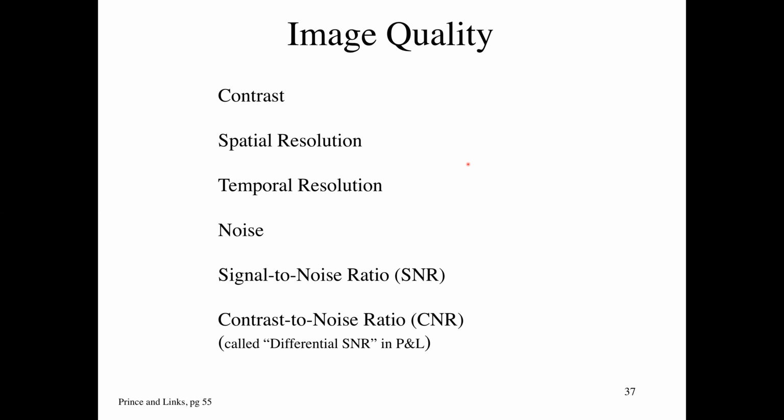Noise in MR is actually a natural phenomenon. If you take a coil and you don't elicit a signal from the patient, but you have your receiver coil that you're going to listen to the signal with, I just hold it away from the patient and look at it on a scope and watch the random noise.